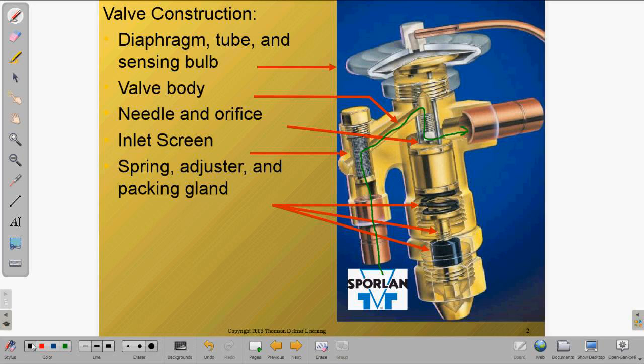Now, the refrigerant that is here in green follows that path and only stays within this part of the valve, so it only follows this path right here. Anything above or below that, the path here has no effect on it. The refrigerant won't flow down into the bottom of the valve or up into the top part of the diaphragm. And I'll just back up here just a bit. It does push up here in the bottom of the diaphragm, and we'll go into that in detail here in just a bit. All right.